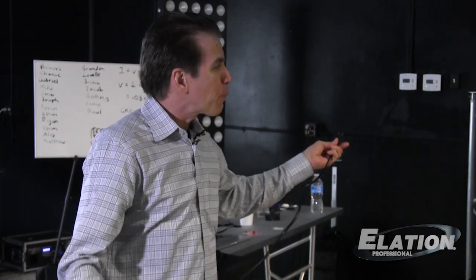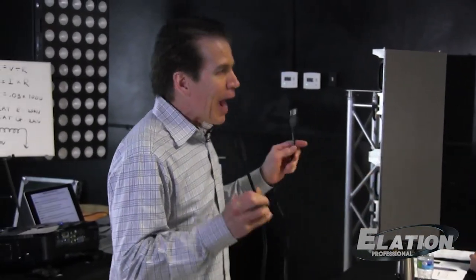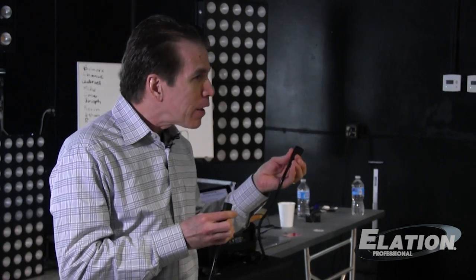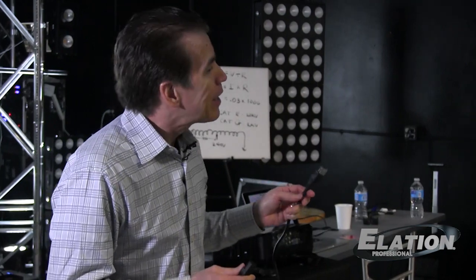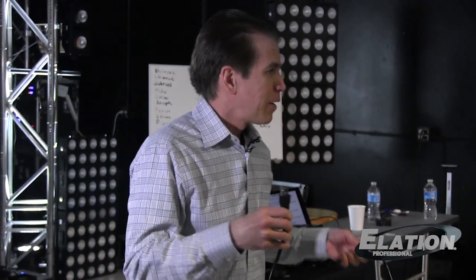Well, when the fixture's all brand new and the cable's brand new, I'm sure it works just fine. But as the thing ages and the insulation breaks down, then it's more and more likely to arc, and arcing leads to heating, and heating leads to more arcing and more heating, and it becomes a vicious cycle until eventually what happens? It melts down and starts a fire, and somebody gets hurt. So use the rating of the connector that's appropriate for the application.